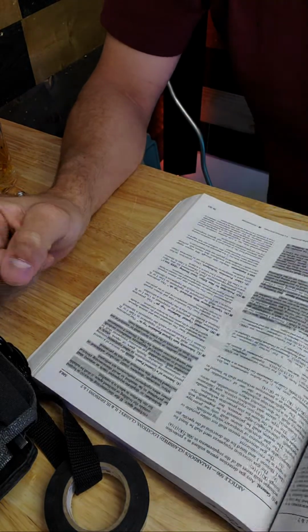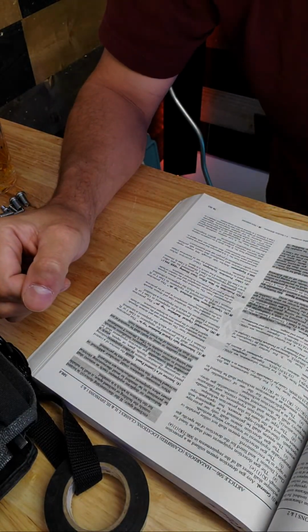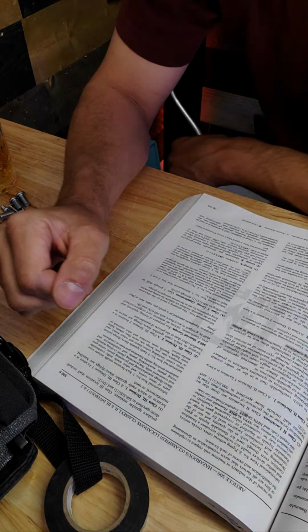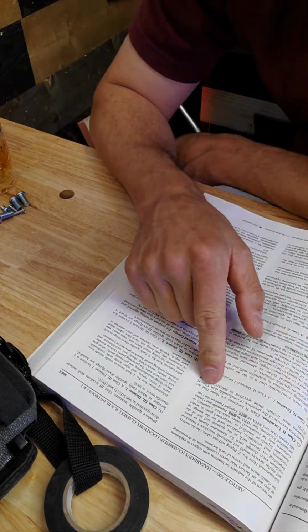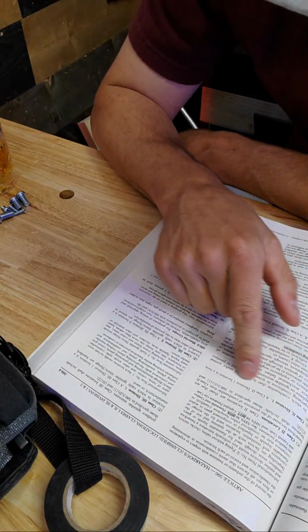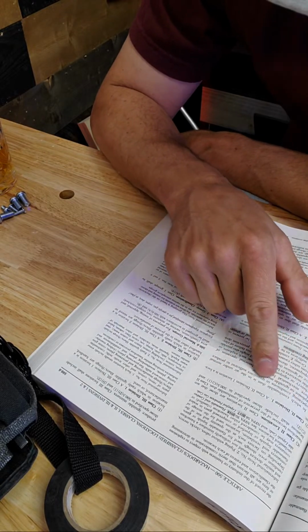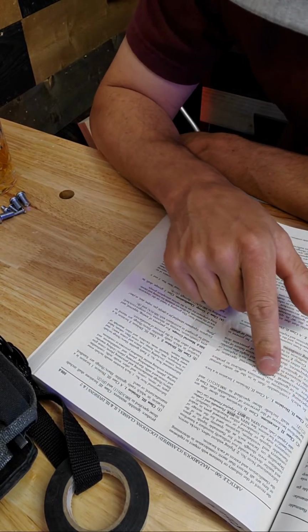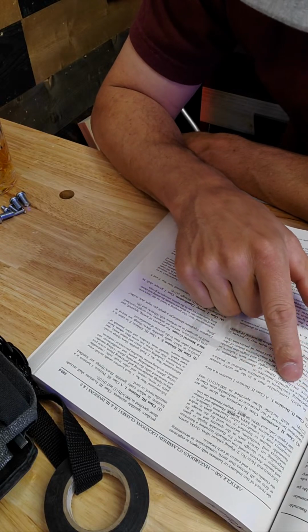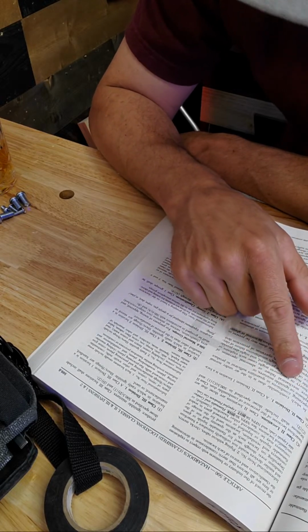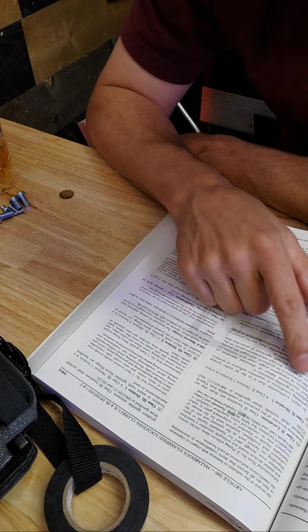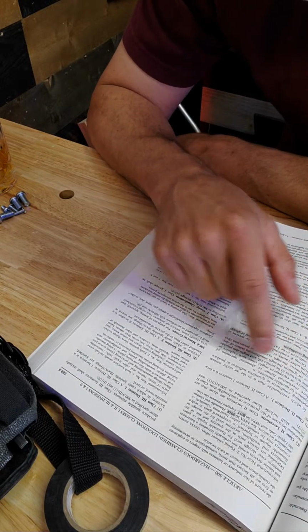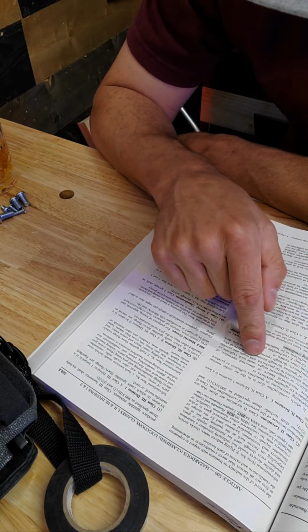So you're going to be in a Class 2, and then it's going to say a Division 1 would be combustible dust in the air under normal operating conditions in quantity sufficient to produce explosive or ignitable mixtures, or a mechanical failure or abnormal operation of machinery or equipment might cause such explosive ignitable mixtures to be produced.